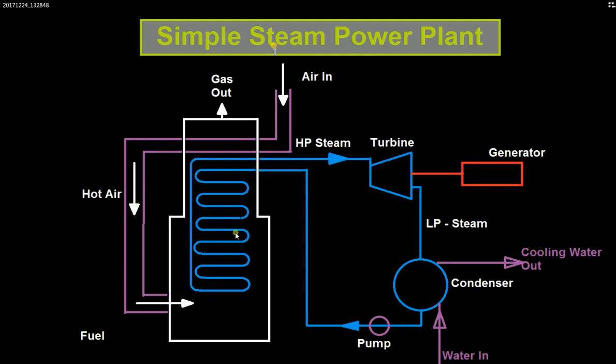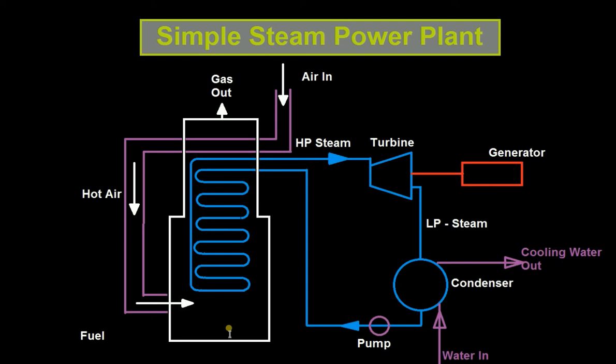Air is supplied in, and as you can see, there is a heat exchanger operating here. As the air passes through it, the air gets hot from the gases going out of the furnace — those outgoing gases still have some temperature in them. That temperature is used to heat the incoming air. The air passes through the heat transfer mechanism, becomes hot air, and is supplied to the system along with fuel to enable combustion.